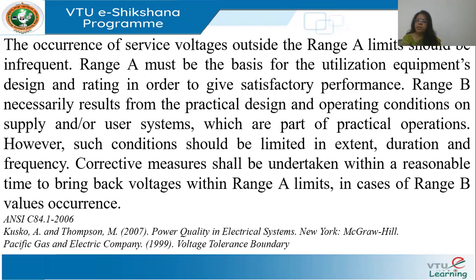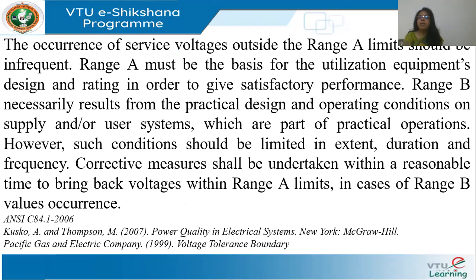The occurrence of service voltages outside range A limits should be infrequent — most of the time the utility should operate in range A, the optimal range. Sometimes it can go to range B, which is acceptable. Range A must be the basis for utilization equipment design and rating to give satisfactory performance, and the manufacturer's guaranteed immunity is for range A voltages.